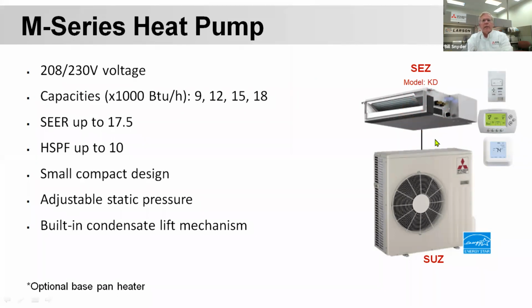It won't do a whole lot of static. So just be aware that you can't put 40 feet of duct on this thing. It's designed for just a few feet of duct and just a couple of takeoffs. On this particular air handler, I'll show you another one in a minute that will do a lot more static. This one is available in 9, 12, 15, 18,000 BTUs. It's about 17.5 SEER, a little bit higher HSPF, 10. It does have an adjustable static, but again, this is a low static pressure unit.